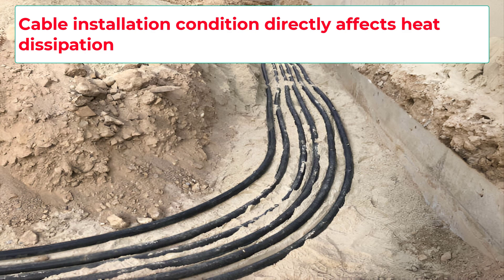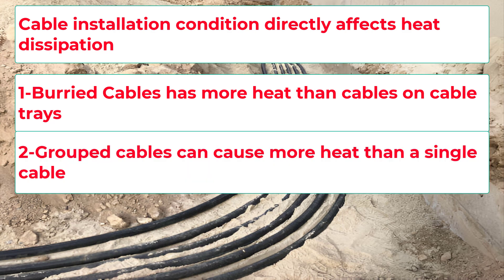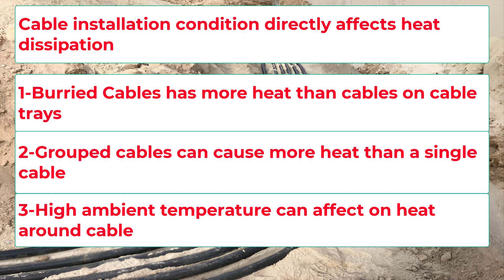Cable installation conditions directly affect heat dissipation. For example, a cable buried underground has less air circulation, so it retains more heat. Multiple cables grouped tightly together cannot release heat properly. High ambient temperatures — like running cables near machinery — mean cables run hotter. Because cables rely on their environment to cool down, each of these factors can reduce how much current they can carry safely.